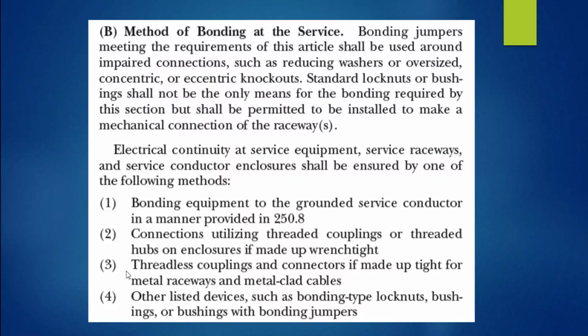All right. Then it goes on to item 3. It says threadless couplings and connectors if made up tight for metal raceways and metal clad cables. Okay, so then also I can have threadless couplings and connectors once I make them up tight, even set screw tight, and it's acceptable. And then 4 says other listed devices such as bonding type locknuts, which we're going to see pictures of in a minute, bonding bushings, or bushings with bonding jumpers. There are bonding bushings that also screw on that serve a role as a bonding bushing, but it also drives into the ring and makes the connection as well. So there are different selections to choose from.